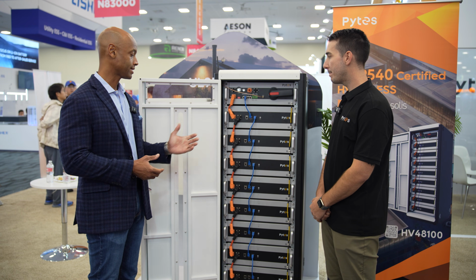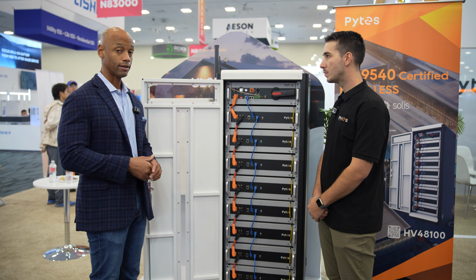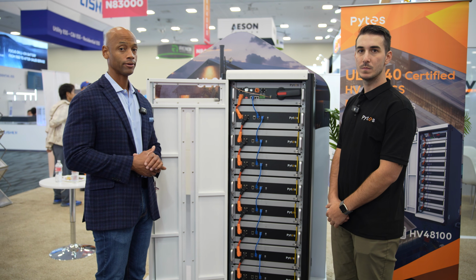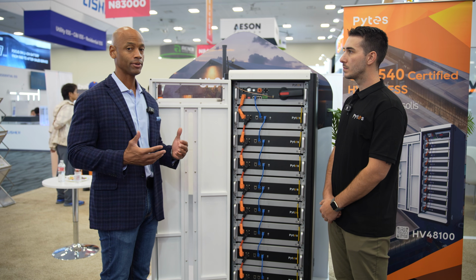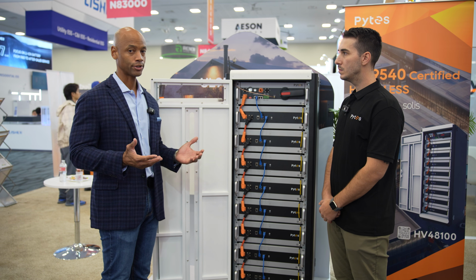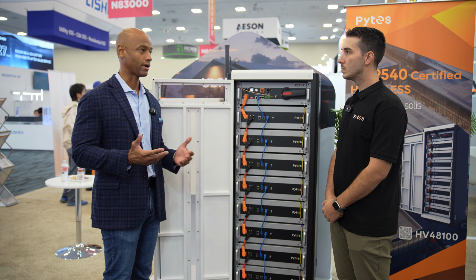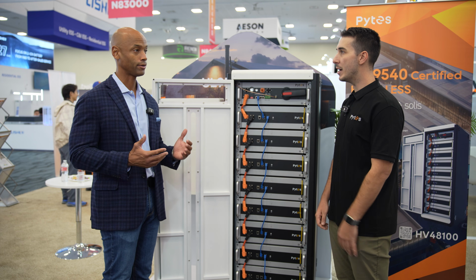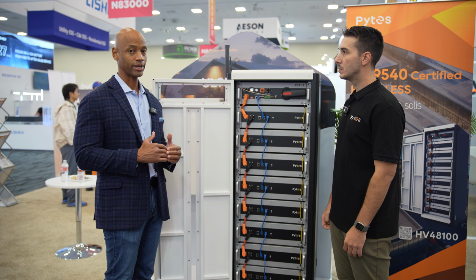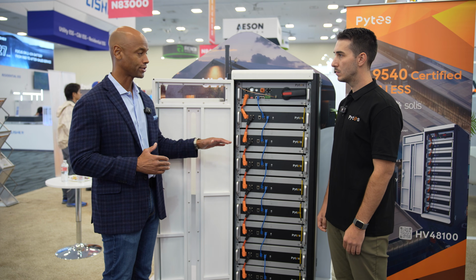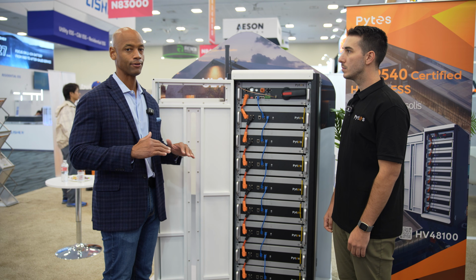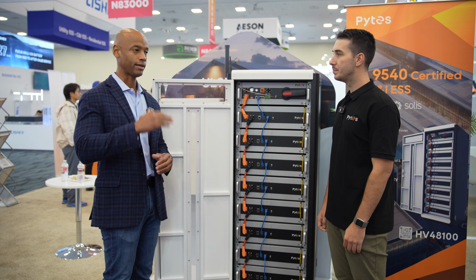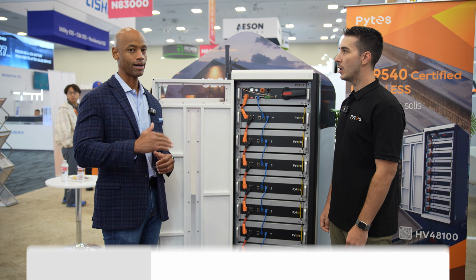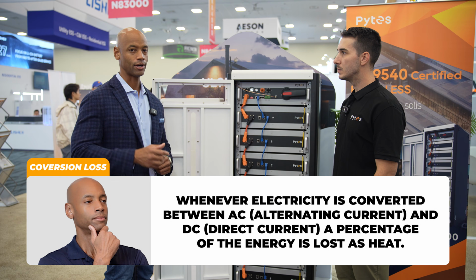The nice thing about the high voltage DC, for those who've been following the channel, solar panels typically are wired at high voltage too, so you might have the solar array wired at 300 to 500 volts. If you can take that high voltage, bring it down to ground level, and do your battery charging that way, it's a more efficient high voltage DC to DC charging than always stepping the voltage up and down, since there's always a little conversion loss whenever you do that.